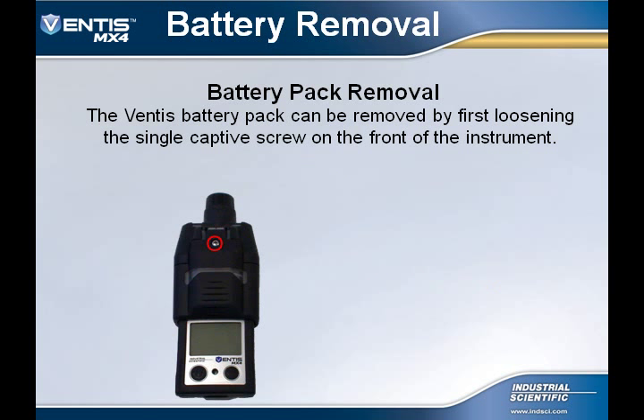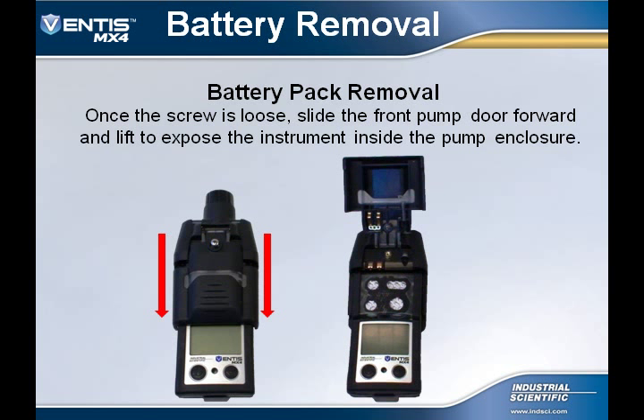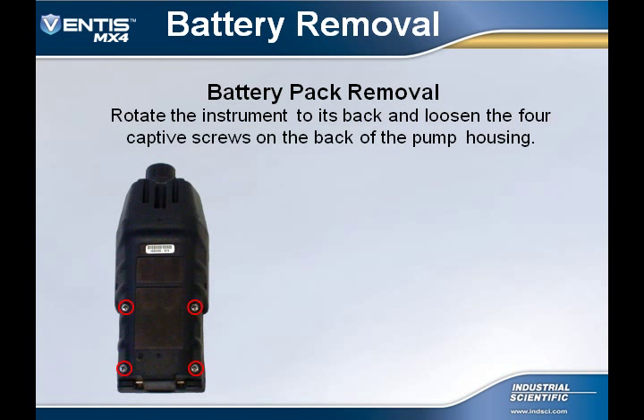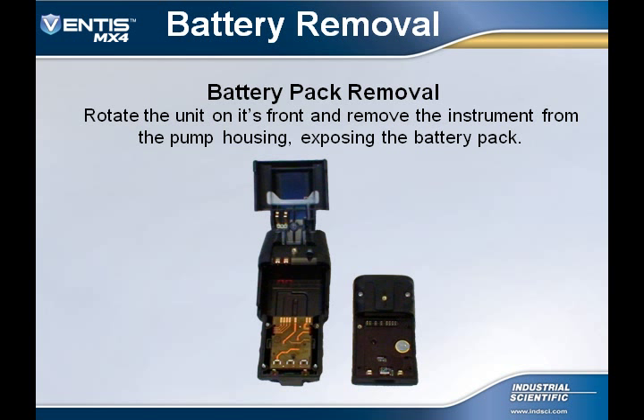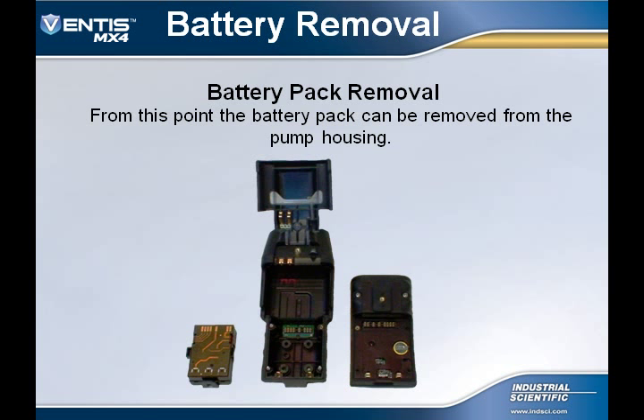To remove the battery pack, first loosen the single captive screw on the front of the instrument. Once the screw is loose, slide the front pump door forward and lift to expose the instrument. Next, rotate the instrument on its back and loosen the 4 captive screws located on the back of the pump housing. Rotate the instrument to its front again and remove the instrument from the pump housing, exposing the battery pack inside. Simply remove the battery pack from inside the pump housing.